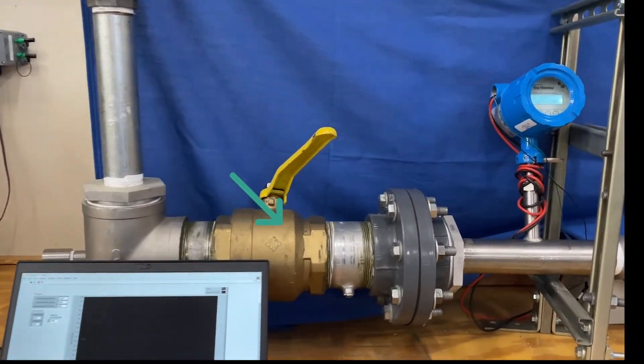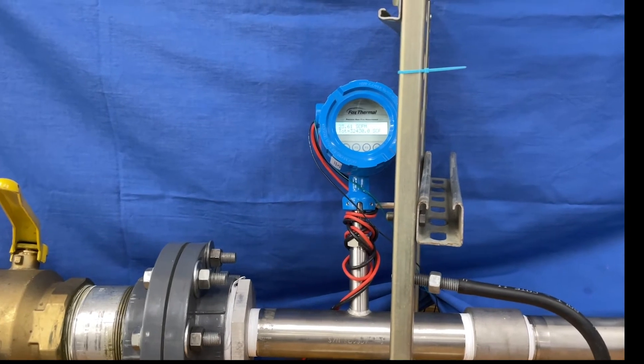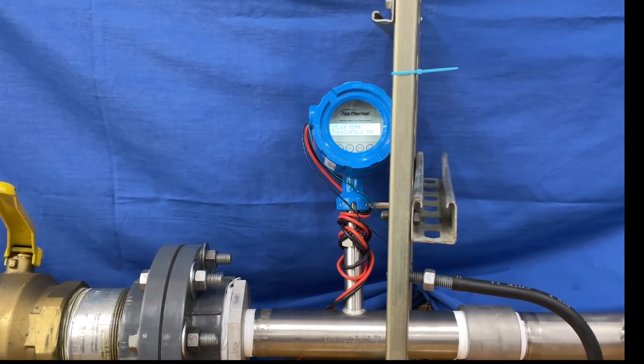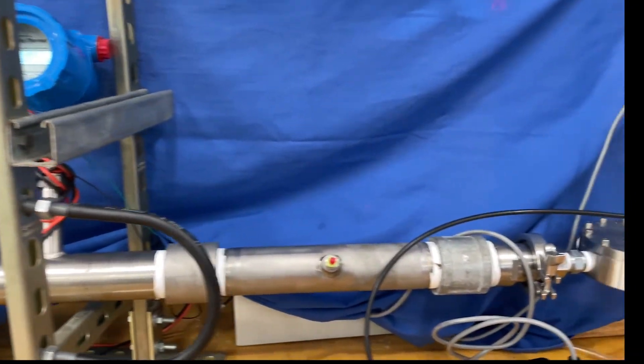The air passes through this ball valve, and then through our flow meter. The range on this flow meter is 0 to 550 SCFM, and the flow meter is outputting a 1 to 5 volt signal to LabVIEW, which is the process value of the PID loop.